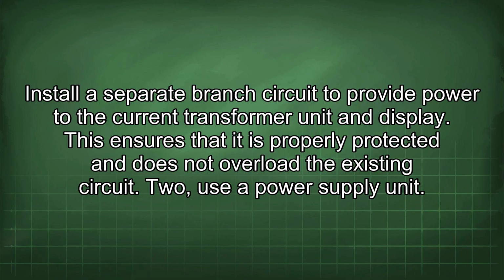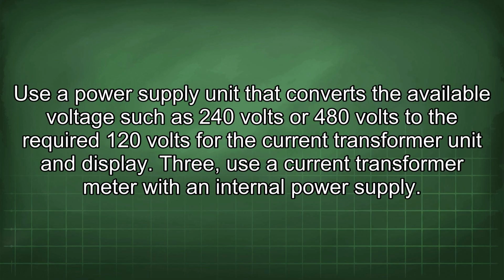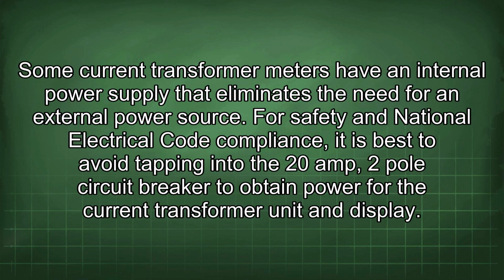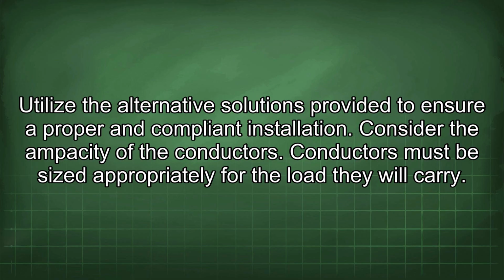2. Use a power supply unit. Use a power supply unit that converts the available voltage, such as 240 volts or 480 volts, to the required 120 volts for the current transformer unit and display. 3. Use a current transformer meter with an internal power supply. Some current transformer meters have an internal power supply that eliminates the need for an external power source. For safety and National Electrical Code compliance, it is best to avoid tapping into the 20-amp 2-pole circuit breaker to obtain power for the current transformer unit and display. Utilize the alternative solutions provided to ensure a proper and compliant installation.